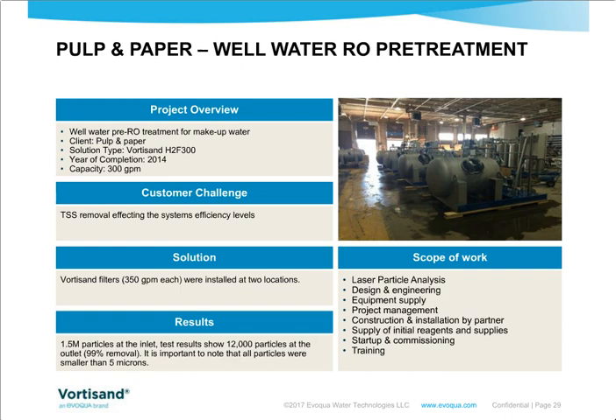Not only is the Vortisand high-efficiency submicron filter used in HVAC or cooling or heating applications, we've also been able to improve pretreatment water quality for a well water RO pretreatment. This is an installation that was done at a pulp and paper facility, where back in 2014 we installed a Vortisand H2F300, removing large quantities of TSS for the pulp and paper mill to operate more efficiently.